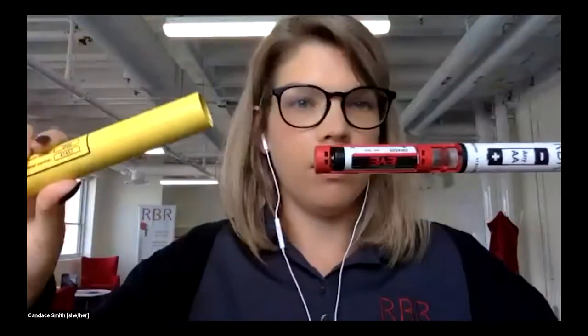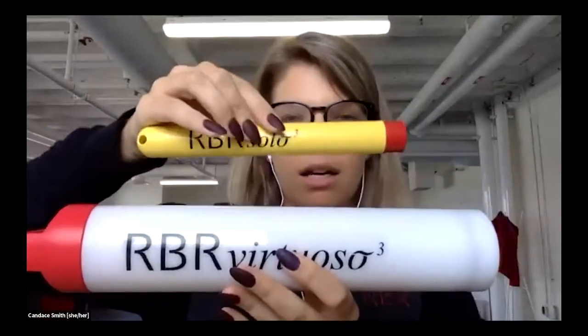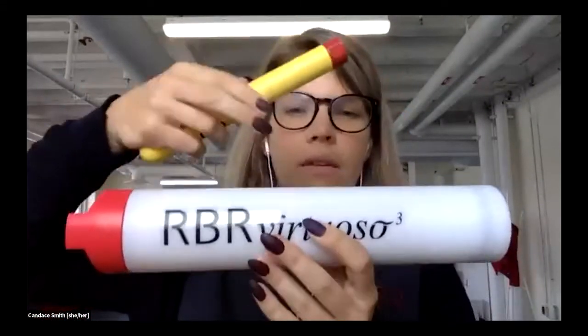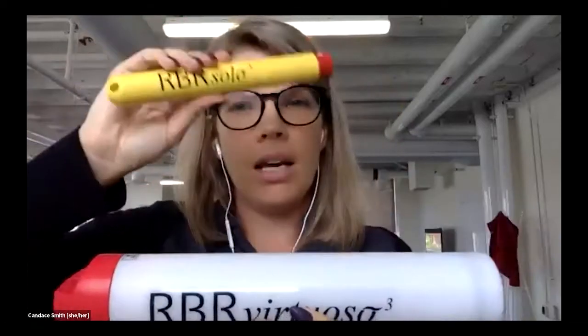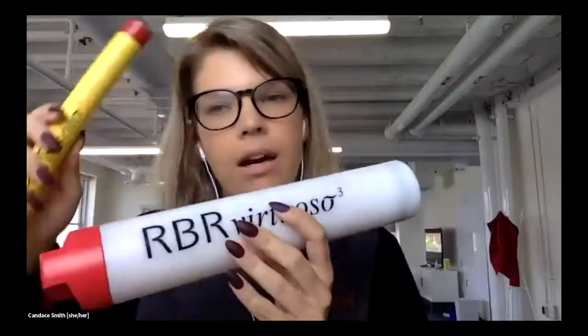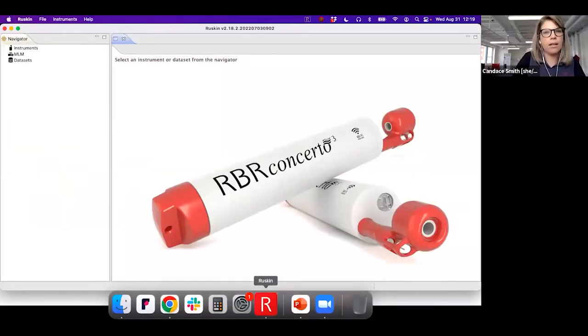Let me show you a couple of these instruments I have on hand. This is the Solo-D Wave 16 — it's really easy to open up, and you can see the battery inside. The next most common wave logger we have is the Virtuoso-D Wave 16. You can see the size difference — the Virtuoso has eight AA batteries, while the Solo has one AA battery. Now I'm going to start showing you Ruskin so you'll see what that means in terms of battery life.